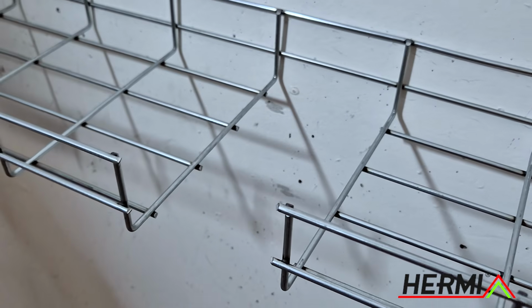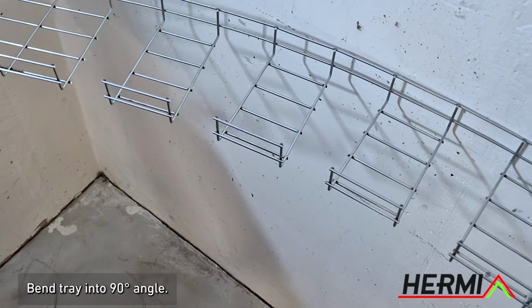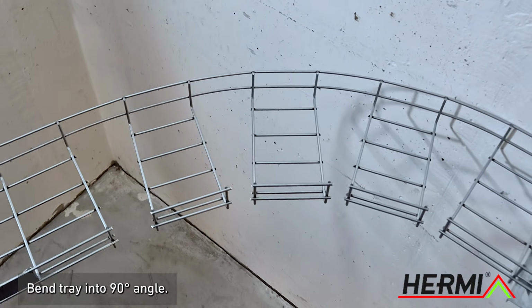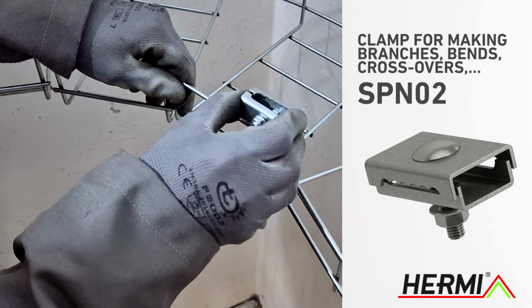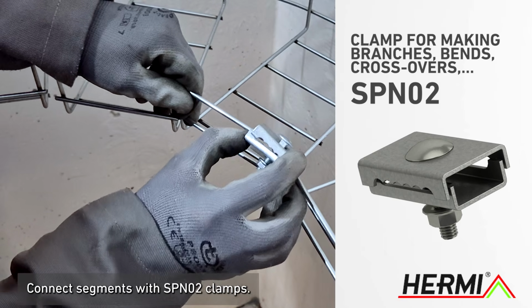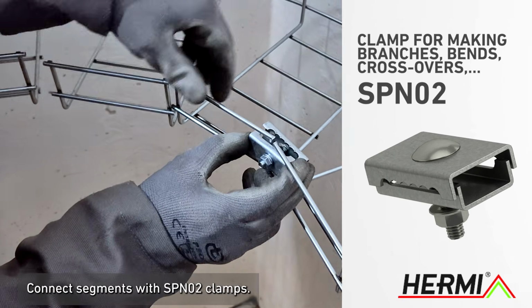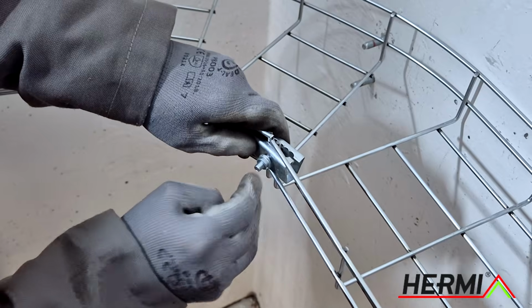Once all the required segments are cut out, bend the mesh cable tray to form a 90-degree bend. Attach SPN02 clamps between the individual segments to hold the bend securely together.